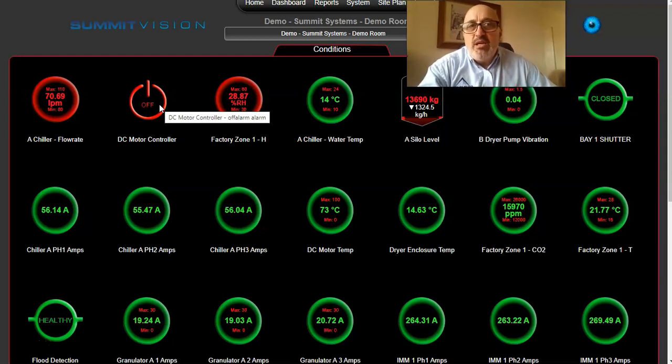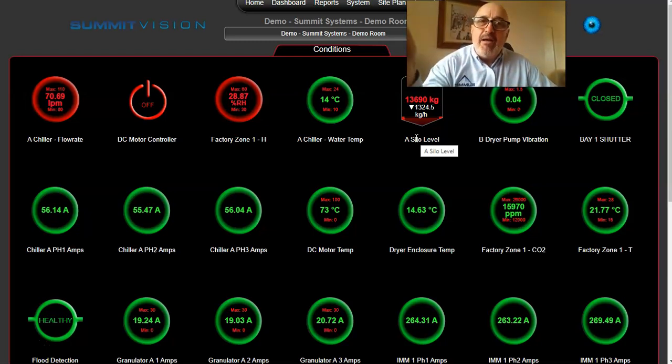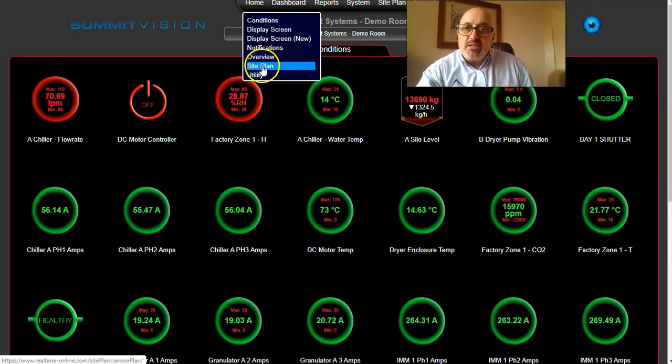Now, that's where we may not have data existing, but clearly on the factory floor you'll have data existing in PLCs that you've got in your local control panels. You're looking at those control panels with the clipboard taking readings, and depends how sophisticated you are and how you're managing that data. We can pull key data off your PLCs, put them into these dashboards here, and give you the analytic capabilities to look and manage that data in a better way and set alarm thresholds if things aren't as you expect them to be. Very, very flexible system. That's one view with these dials and these limits, but also we can see it on a site plan view.